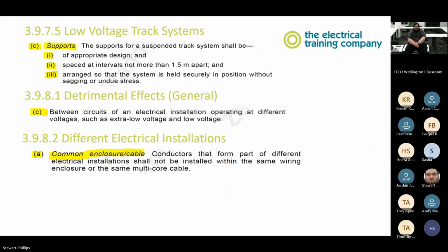Induction. So basically what it's saying is if you have two cables, one from one house and one from another, they should not be installed in the same wiring enclosure or same multi-core cable. This is to make sure that a dead short in one installation does not affect another.